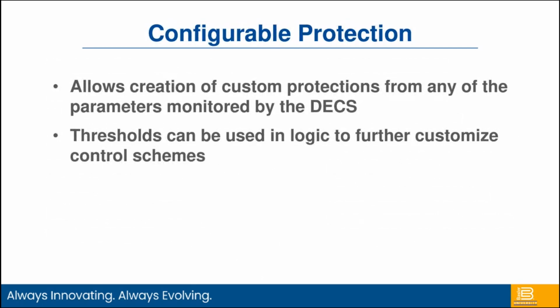And if there's something in the application that is not in the DECS as far as a protection function, we can do configurable protection. So this is a really useful tool that's integrated into our software. It allows you to look at basically any parameter that the DECS is monitoring, and you can set up thresholds or limits, and you can use these to do protective functions or control functions. So it's just a very configurable and flexible way to add additional features into your excitation or into your voltage regulator system.